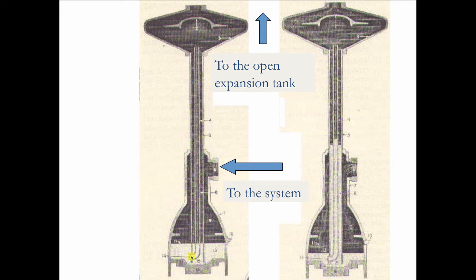There's a lot of mercury inside this thing, and there's a pipe within the pipe. This goes up to the expansion tank in the attic, and this is connected to the system. The water in the system is isolated from the water in the tank by a dip tube that goes down into the mercury. When the water in the system begins to heat and expand, it pushes down on the mercury, causing the mercury to rise up the interior tube — kind of like the diaphragm on a compression tank going in and out as the water heats and expands. That's how he's able to have 250-degree water at 15 psi in liquid form and still have the system open to the atmosphere. And the safety feature was that should pressure get too high, the water would access the internal pipe and safely relieve itself to the attic expansion tank.